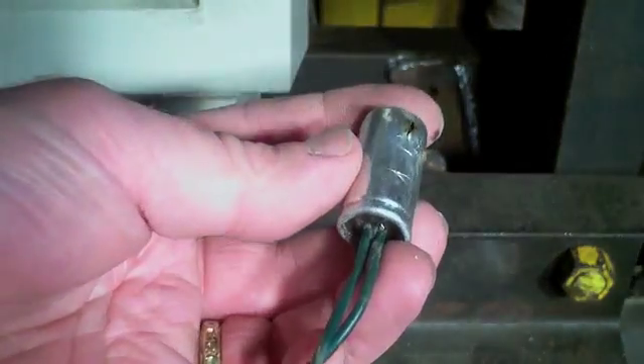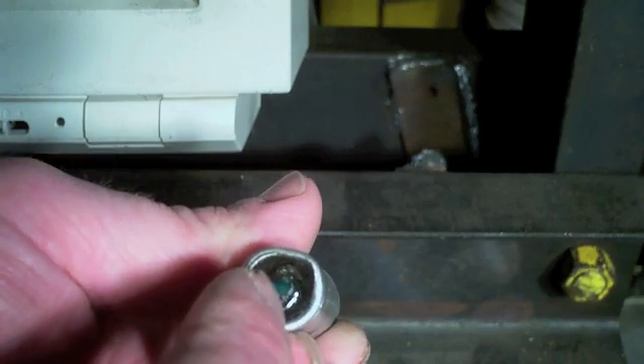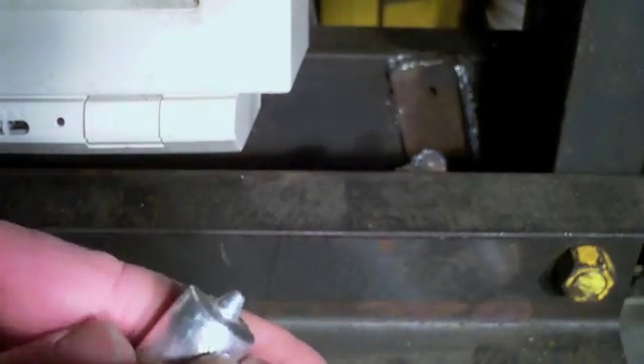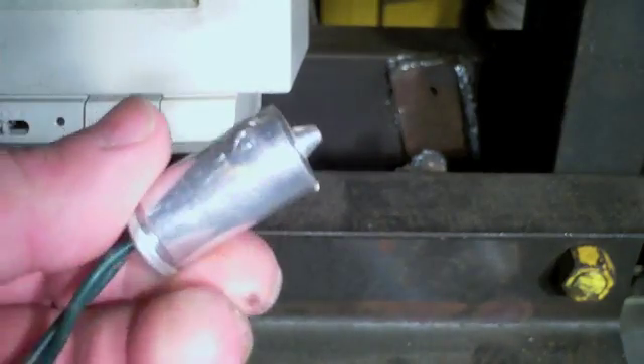Fascinating, fascinating. I mean, it's really encased. There is a bubble down in there — wasn't there before. The epoxy's gone a touch gummy from the heat. But it appears to have vented out of the capacitor on the inside, then blown through the wall of the capacitor on the outside — this aluminum shell. So we're back to square one again.